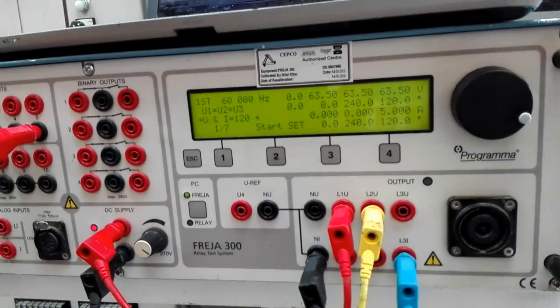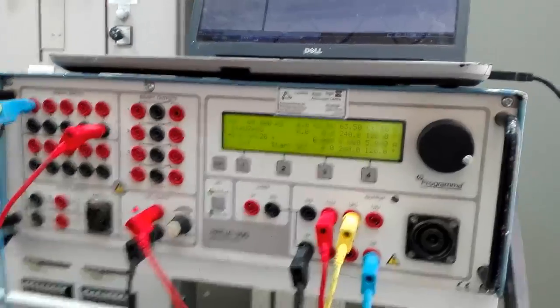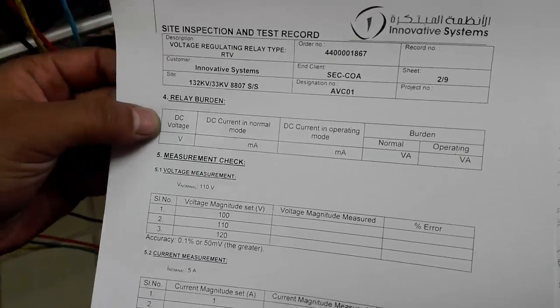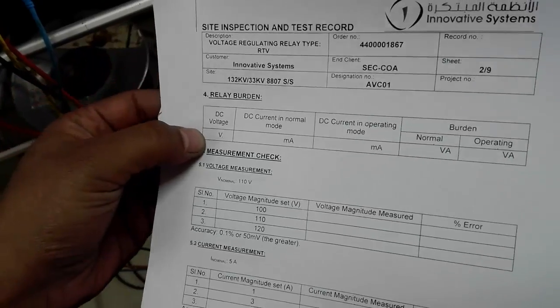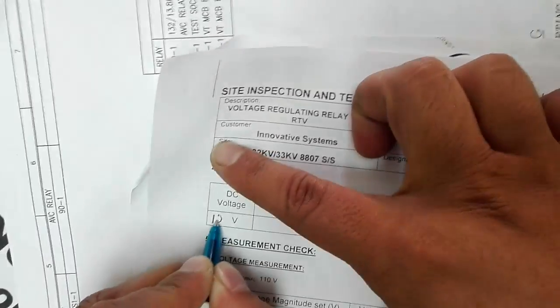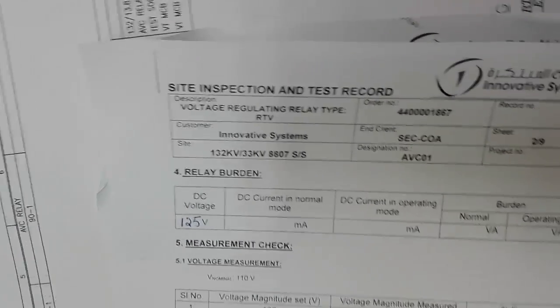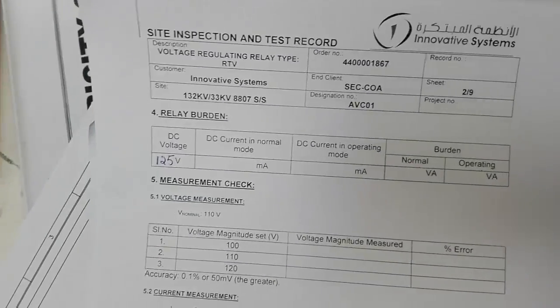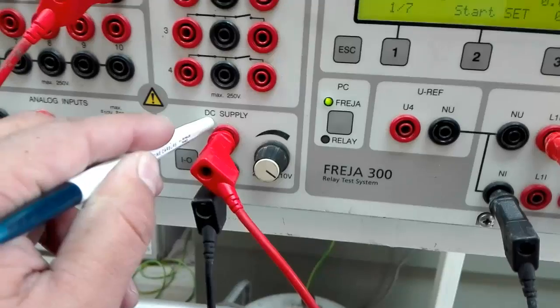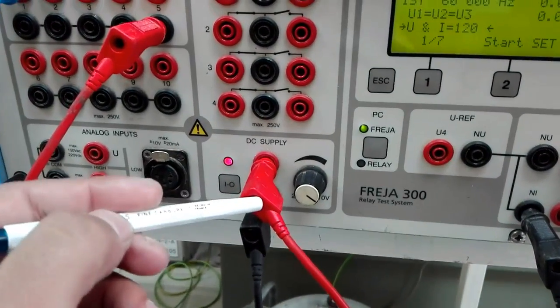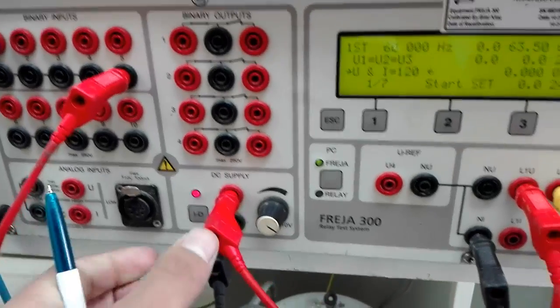Now after completing the connection side, we have to inject according to the test format. For the relay burden, the rated DC voltage will be 125 volt. So first, simply we will inject 125 volt DC. Yes, we have made the arrangement for this. This is the DC supply in the Freja box. R, and this is neutral. We already measured it, it is applied as 125 volt.